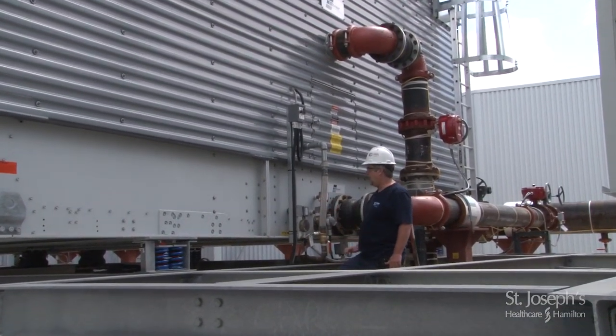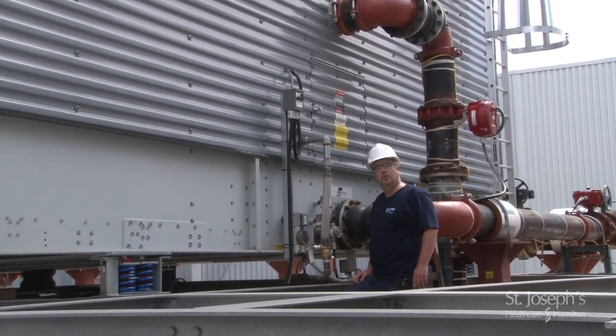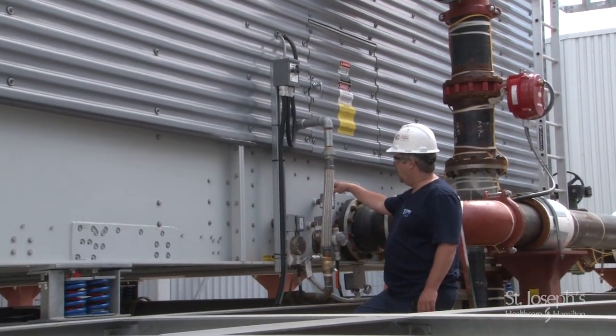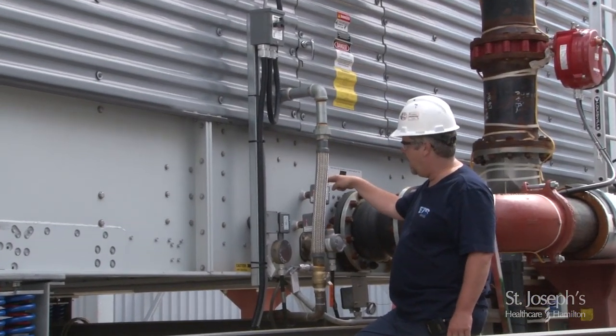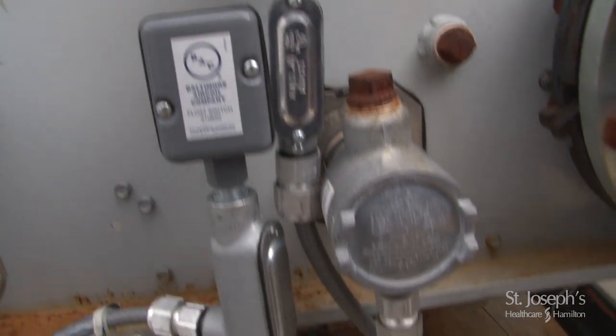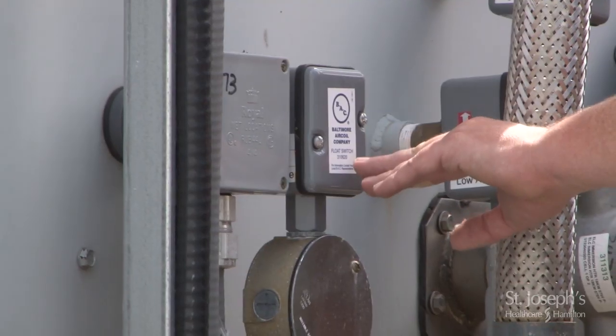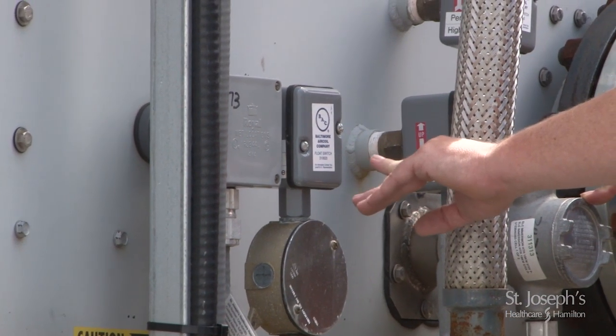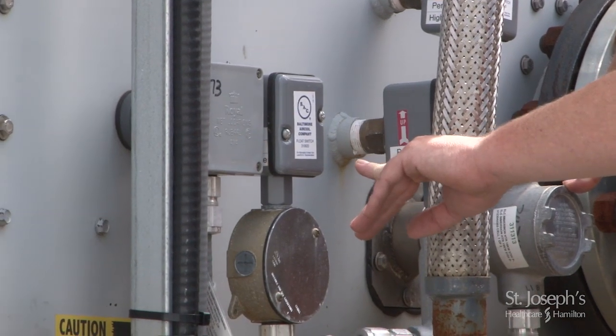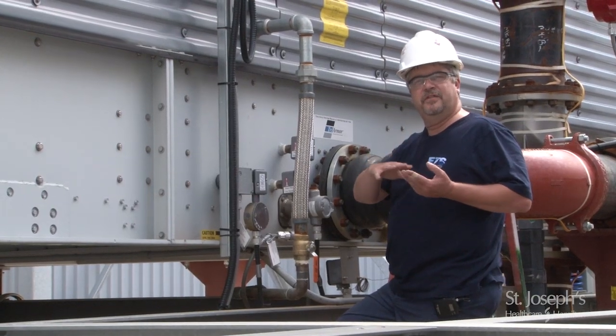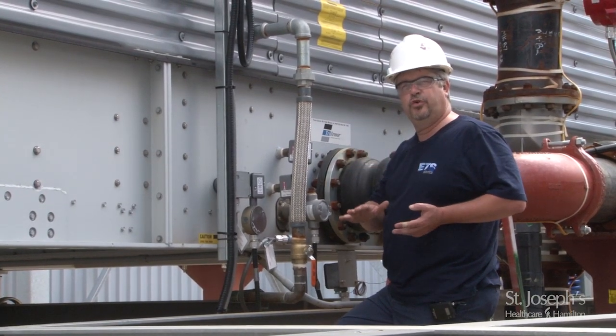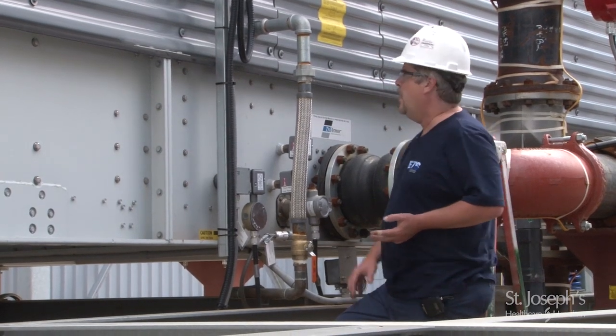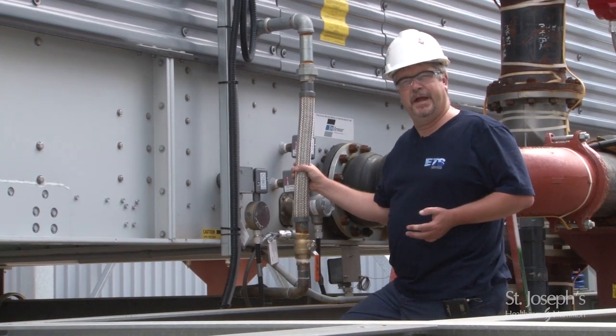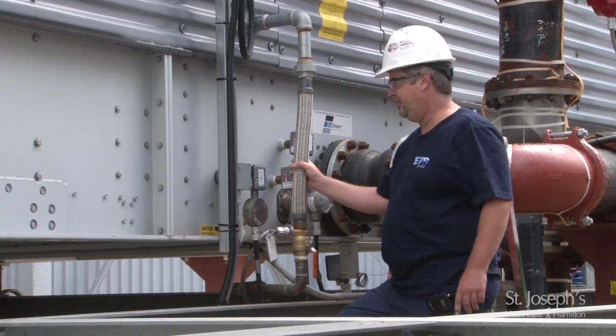You'll see that there are some added connections on the side of the winter tower. Like the other tower, we have our high alarm. We also have a low alarm cutout switch. Basically, what those switches are designed to do is to warn the operators of the tower if the water level gets critically low within the tower. Maybe something's gone wrong with the makeup and it's not making up water fast enough.